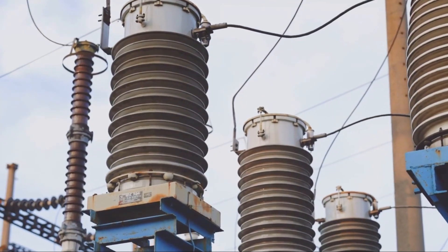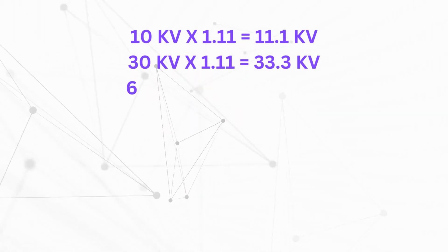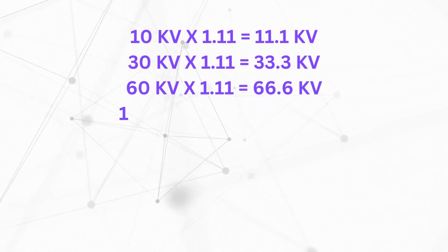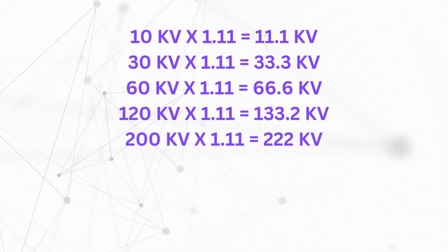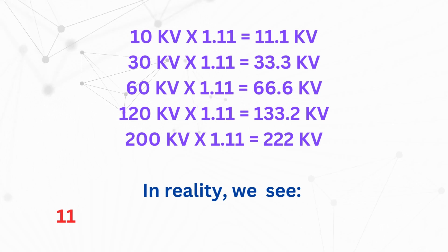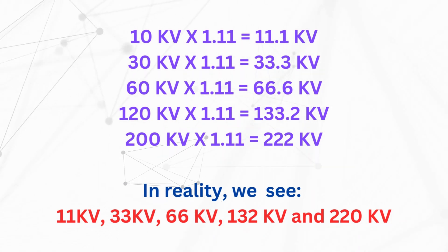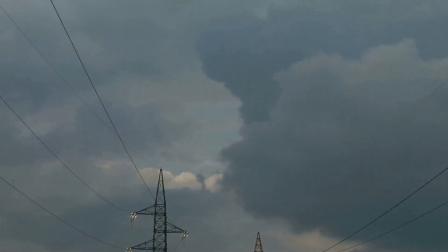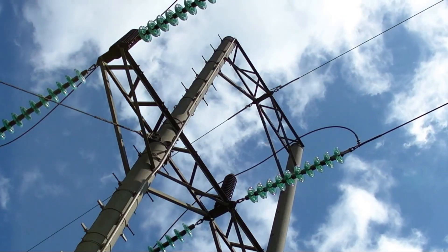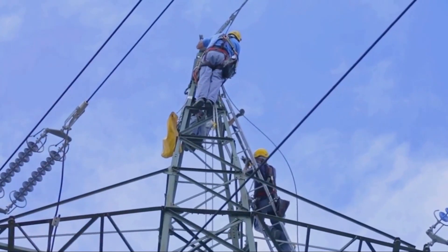Consider this: if we were to strictly follow the form factor, we'd expect to see voltages like 11.1 kV, 33.3 kV, 66.6 kV, 133.2 kV, and 222 kV. But in reality, we see voltages like 11 kV, 33 kV, 66 kV, 132 kV, and 220 kV. These figures don't exactly align with their theoretical form factor counterparts. This discrepancy tells us that the form factor isn't the driving force behind the selection of transmission line voltages — it's a piece of the puzzle, but not the whole picture. So if it's not the form factor, then what?